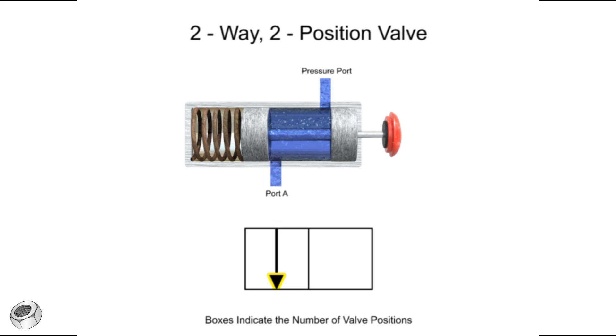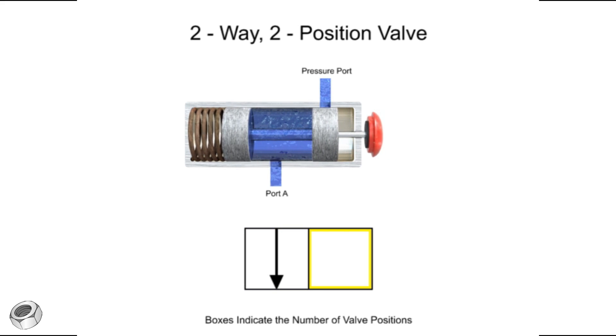A solid arrow indicates the direction of liquid flow. The first position of this valve allows fluid to flow from the pressure port to port A, so an arrow is drawn in the first box to indicate fluid flow. A T indicates that a port or way is blocked or closed. This valve's first position has no ports blocked, but its second position blocks both. Two T's are added to illustrate the lack of fluid flow in the second position.